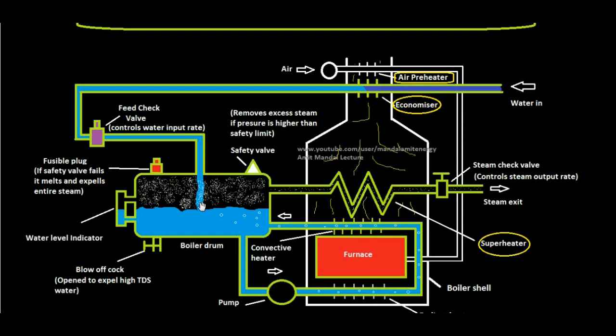Beyond a particular level, if the salt rises, then the entire water is dumped by opening this blow off cock, and fresh clean water is again filled inside the boiler. So this is the job of the blow off cock. It is opened when the salt level of the water goes beyond a particular limit.